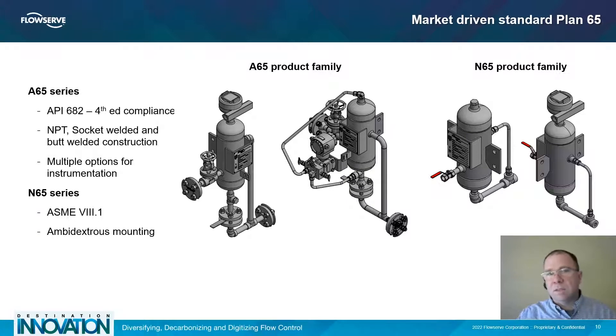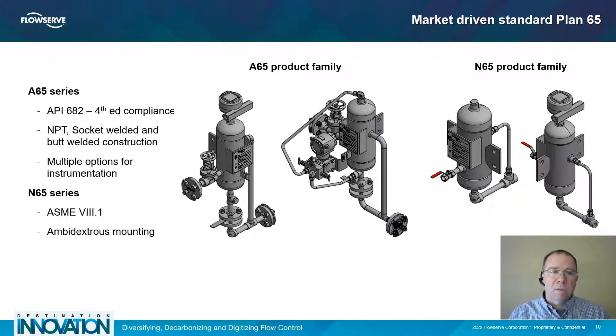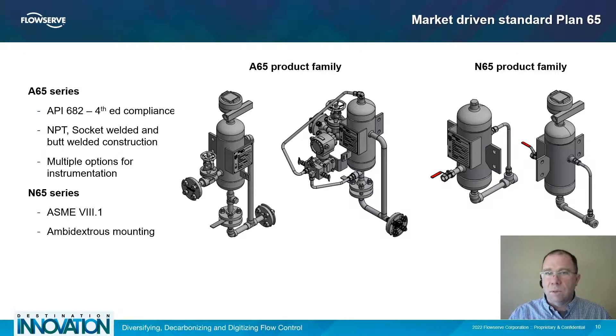The final piping plan we're going to talk about today is the Plan 65 products from Flowserve. Our standard Plan 65s come in two different configurations. The first is the A65 series — a fully compliant API 682 fourth edition piping plan. It comes standard in three different construction options: all-NPT construction, socket welding construction, or butt welding construction. This product family features multiple options for instrumentation. For customers that do not require API 682 fourth edition compliance, we have the N65 series, which is a lower cost general industry duty piping plan designed to ASME Section 8.1. It features ambidextrous mounting configurations and also has a number of different instrumentation options.